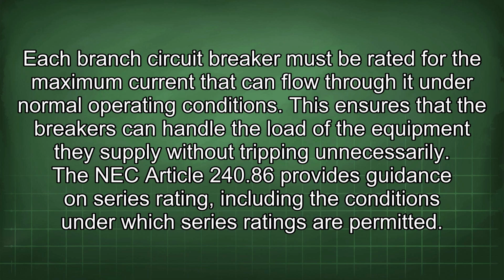Each branch circuit breaker must be rated for the maximum current that can flow through it under normal operating conditions. This ensures that the breakers can handle the load of the equipment they supply without tripping unnecessarily.